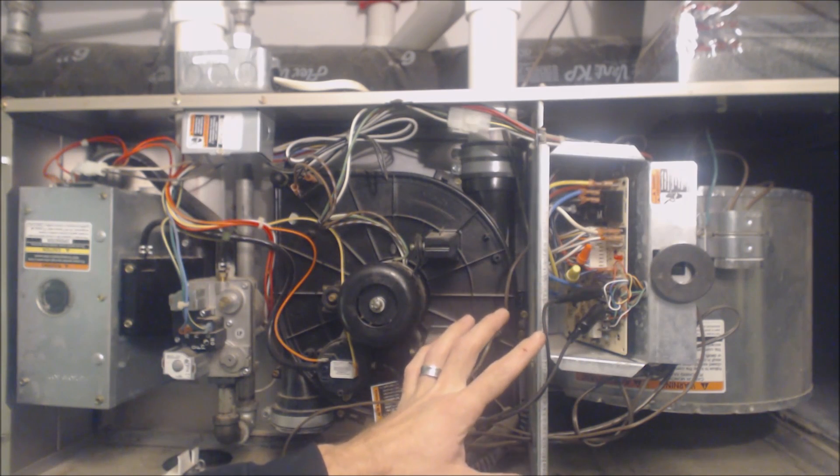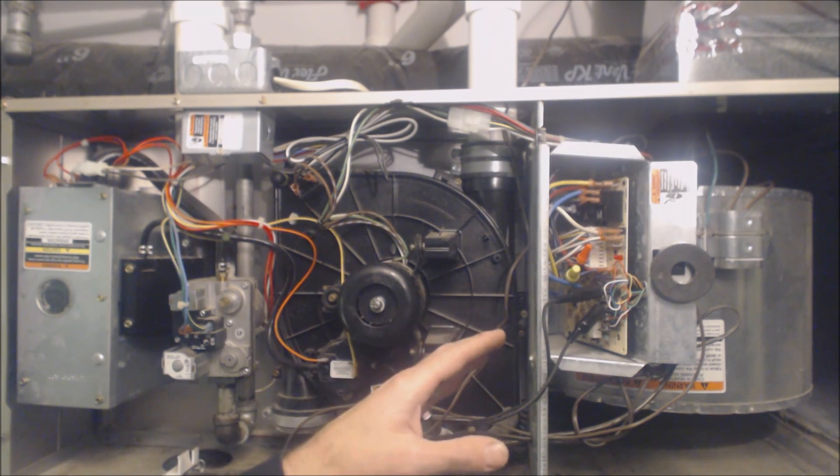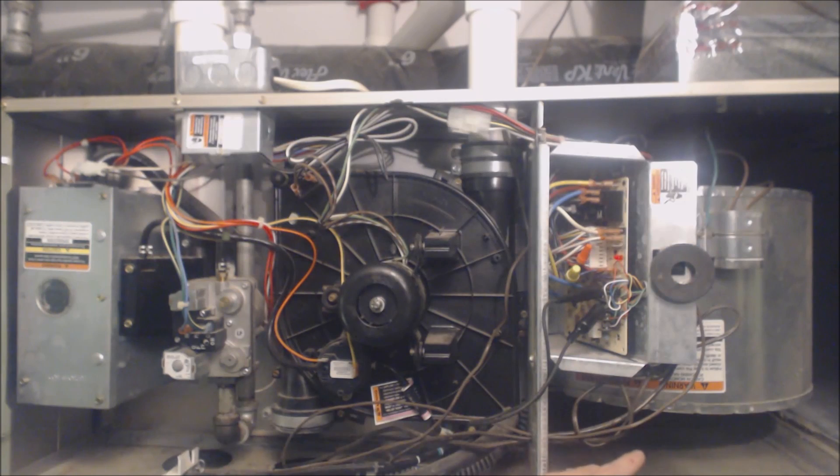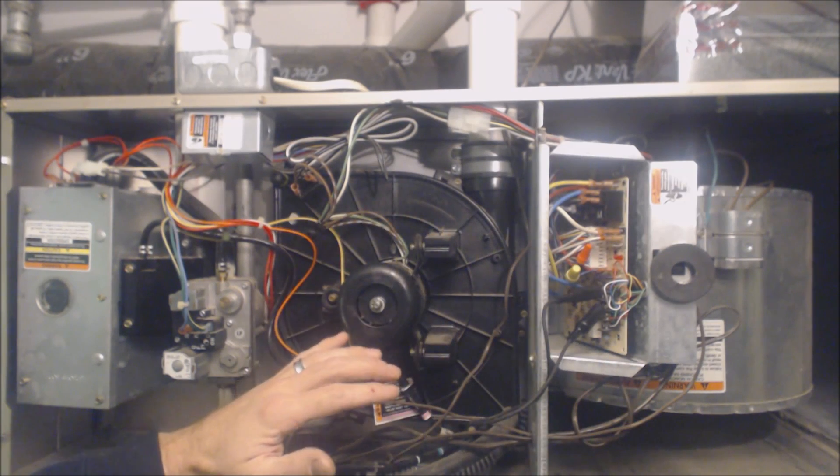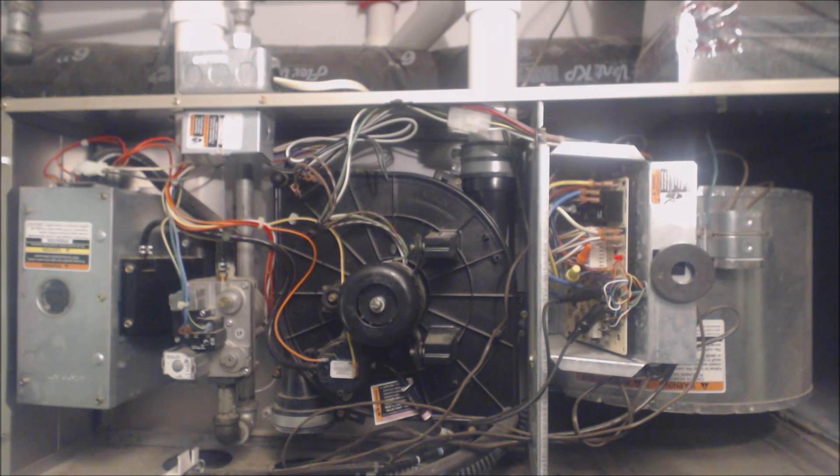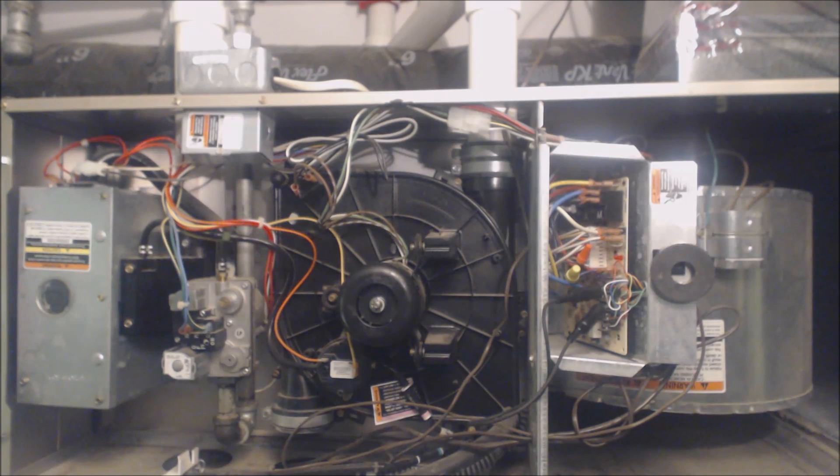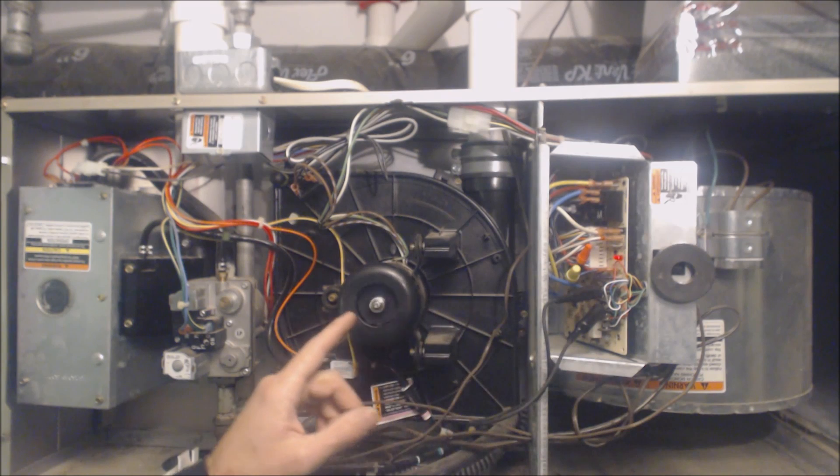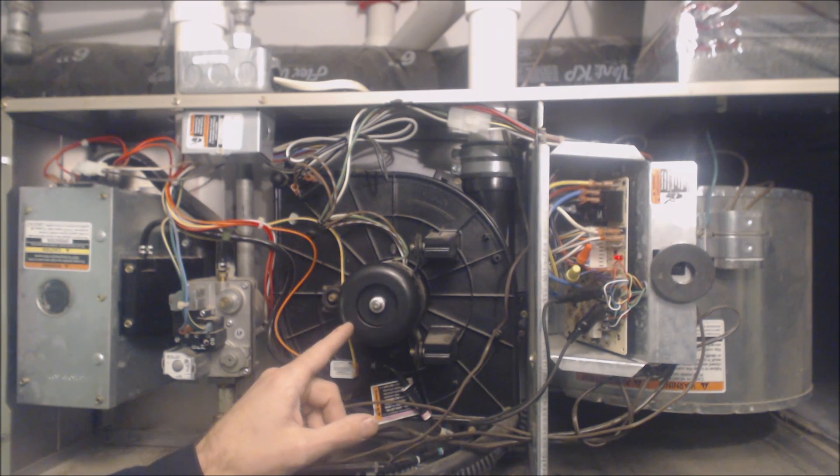Every furnace is built differently. But this particular one, the furnace will run the blower motor for four minutes and then it'll enter into a lockout status where somebody will have to turn the power off and turn it back on in order for it to run again. So right now we're just waiting for the blower motor to shut off. And then after that, there we go, the inducer motor turns on first.